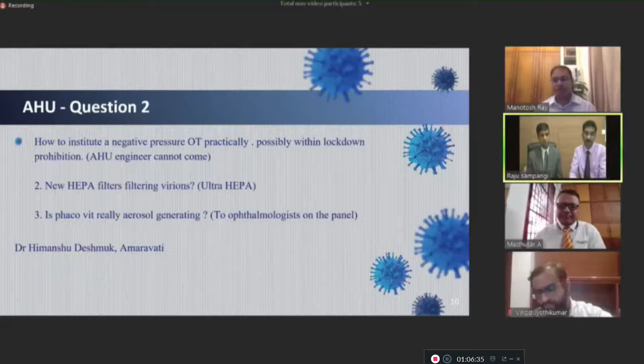A normal operation theater cannot be converted to a negative pressure operation theater without an HVAC engineer visiting the site. It's not possible to just try a fan or anything else without an HVAC engineer, because this involves a lot of detailing with respect to the design. For example, if you have a split air conditioning system and you want to bring in an air change, or fresh outside air, to create that air change...